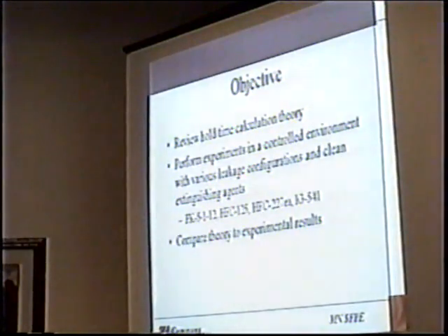So the objective here, once again, is to look at some of the existing calculation theory. This theory has existed in the form that I'll present it to you since the first version of NFPA 2001 came out in the original draft. We're looking at 4 different agents. HFC 227ea, or FM 200, actually was not done by the present research team. The results are subject to a little bit of question, slight uncertainty. You'll see towards the end that the results aren't quite as good, so we're going to be retesting that one pretty soon this summer. We're also looking at FK 5-1-12 or Novec 1230, HFC 125 or the Ecaro system, and Inergen or IG 541. And then, of course, we'll be concluding by comparing the results of our full-scale testing to the theory.